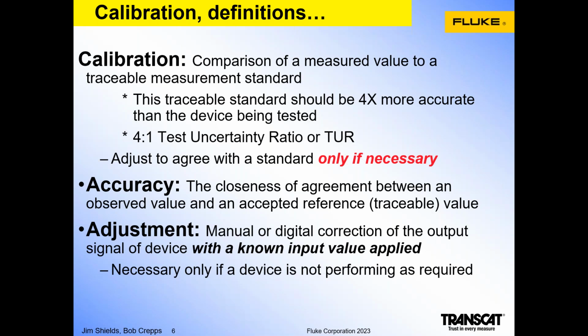And in the case of this intercomparison, this traceable calibration standard should be, as a ballpark, 4 times more accurate than the device being tested. That's the most common rule of thumb in process that I've encountered. There are some other definitions of test uncertainty ratio, or TUR, that I've heard.